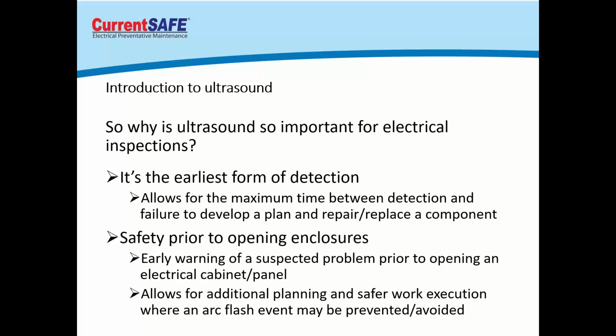One benefit of using this tool, the UltraProbe 10,000, is that we can see the amount of turbulence going on behind that cover or inside the electrical equipment enclosure, and we can record that and tell the severity based on how many decibels it is. That's a technique I use to teach technicians. If you have something really bad, it's going to put out a lot of turbulence, so you're probably not going to want to open that cover without additional protection.